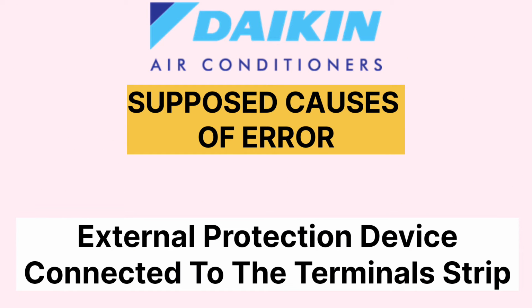Let's see the supposed causes of error A0. According to the definition, it says that external protection device connected to the terminal strips are not correctly connected. Due to that, you get the error A0.